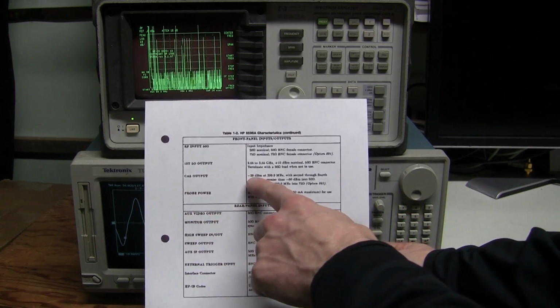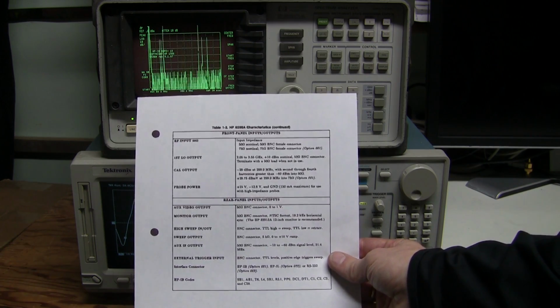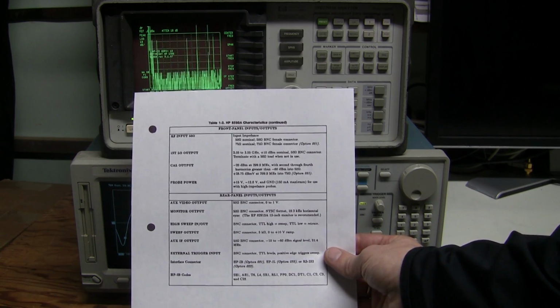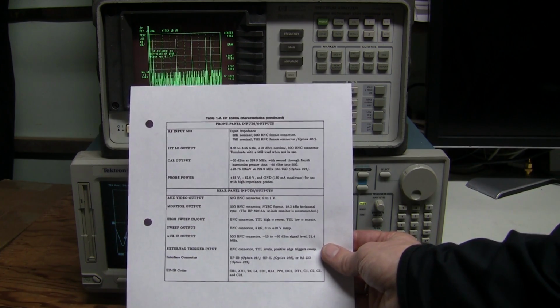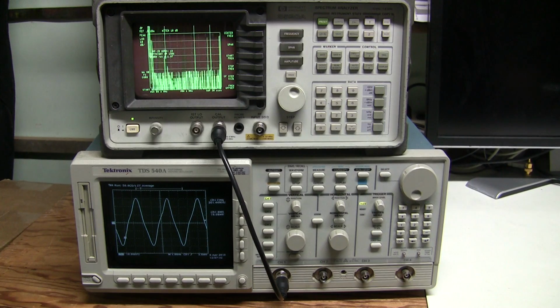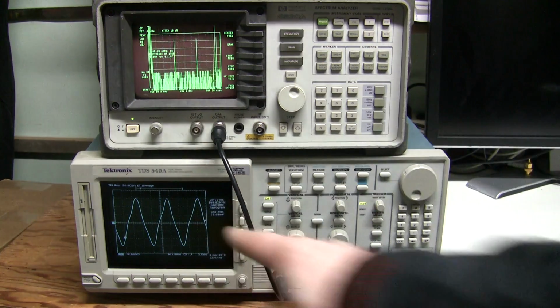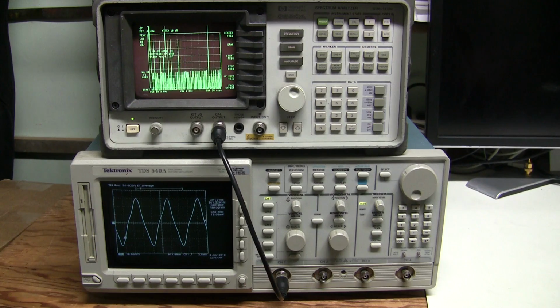And calibration output must be minus 20 dBm, 299.9 MHz, with second through fourth harmonics greater than minus 60 dBm. So it must have intentionally high harmonic content, and we see that the sine wave is not quite a sine wave, it is distorted because of this high harmonic content. And yes, it is about 300 megahertz, and minus 20 dBm corresponds to about 22 millivolts RMS. And we see here 19 millivolts RMS. Close enough, I think, for the accuracy of the scope. So the calibration signal looks good to me.